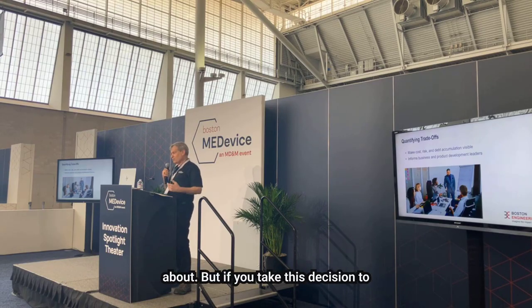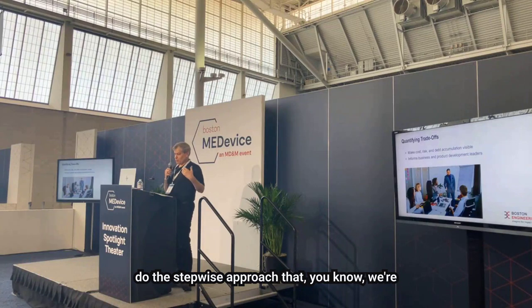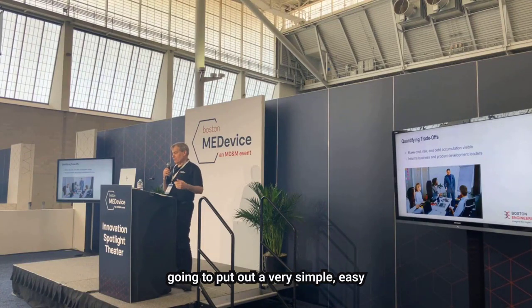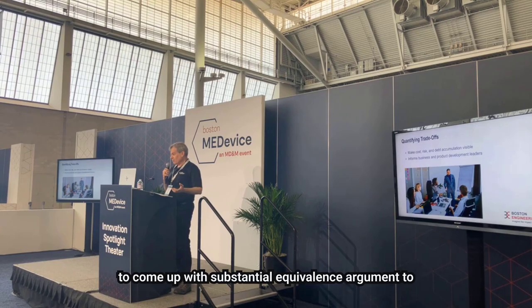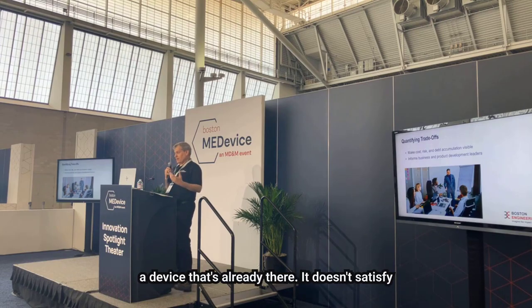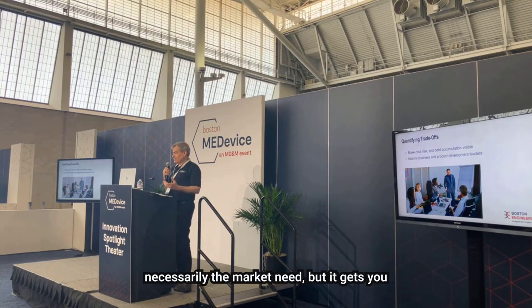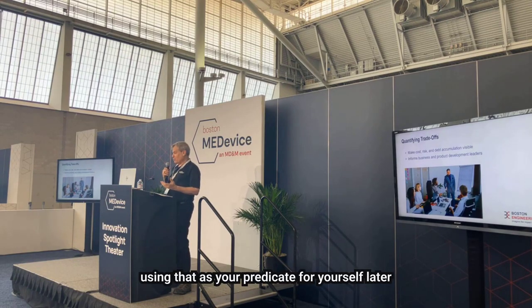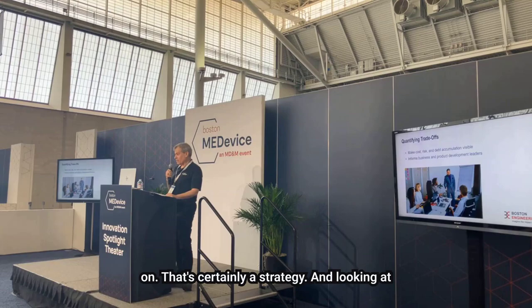But you take this decision to do a stepwise approach: we're going to put out a very simple product, easy to come up with a substantial equivalence argument to a device that's already there. It doesn't necessarily satisfy the market need, but it gets you on the market, and then you end up using that as your predicate for yourself later on.